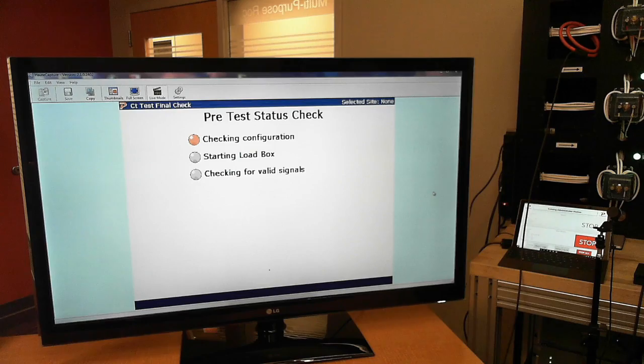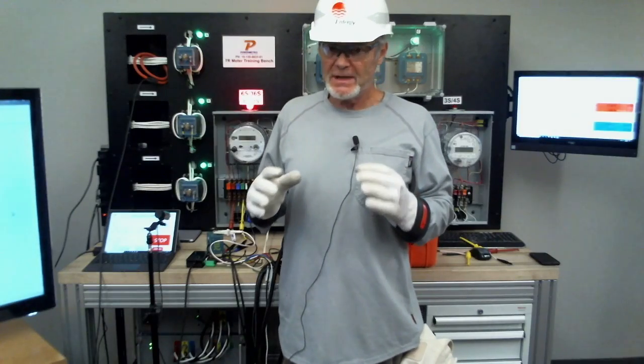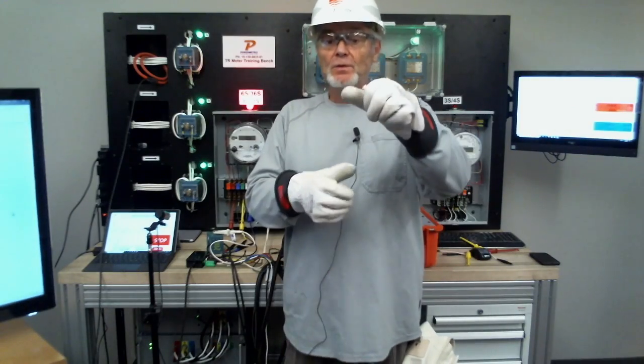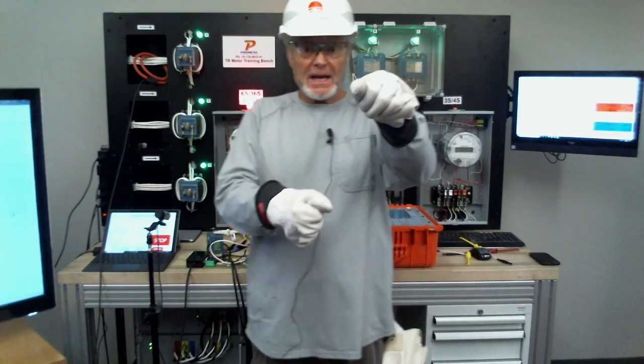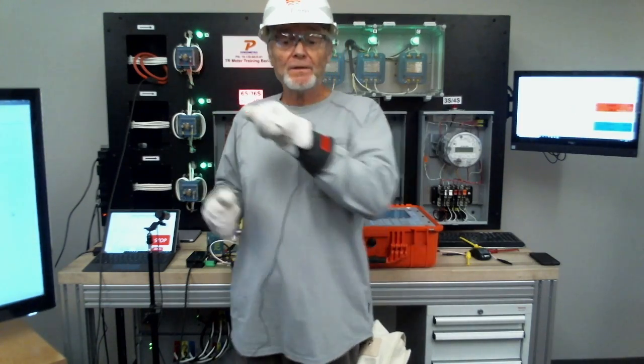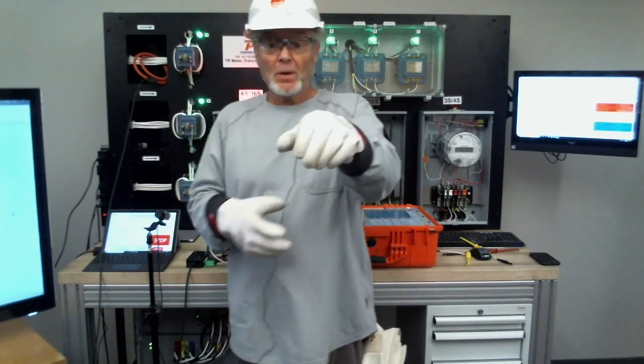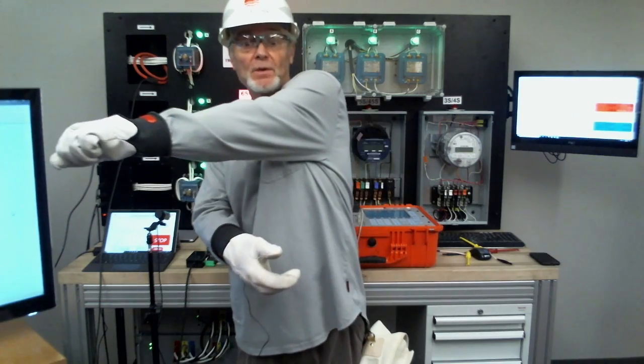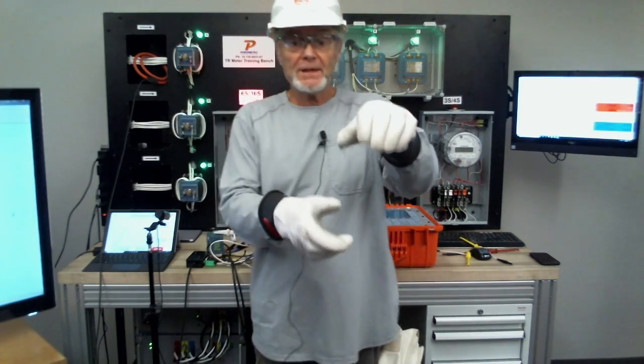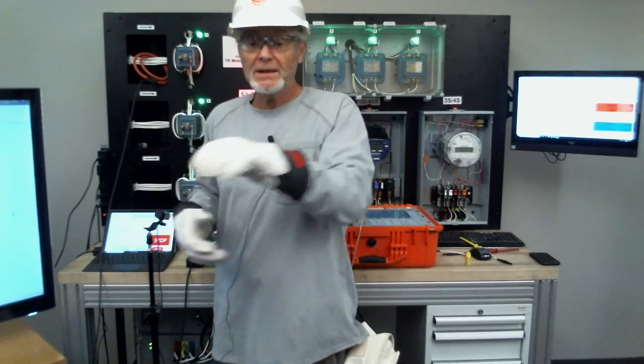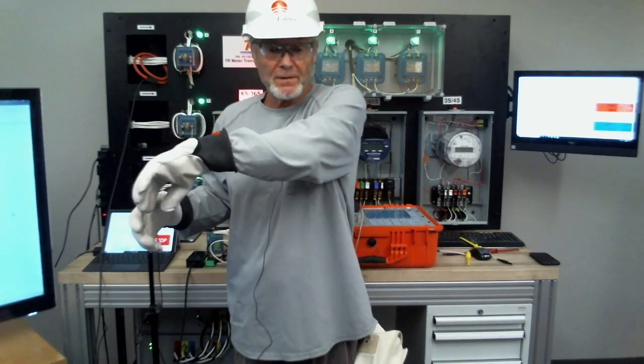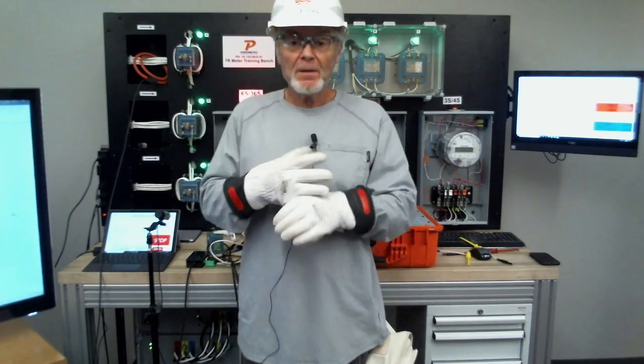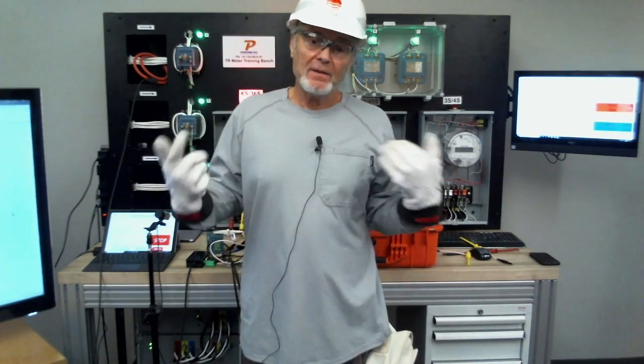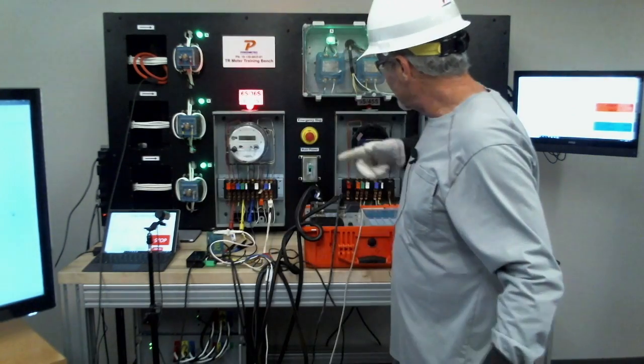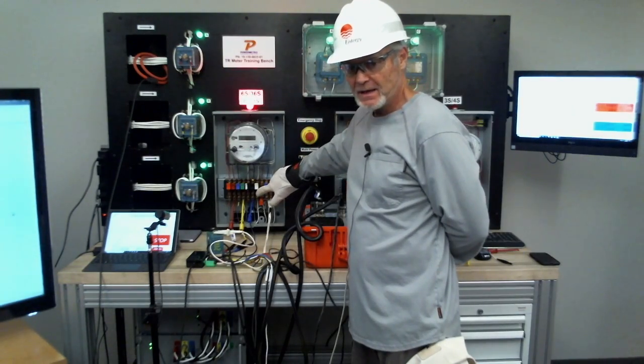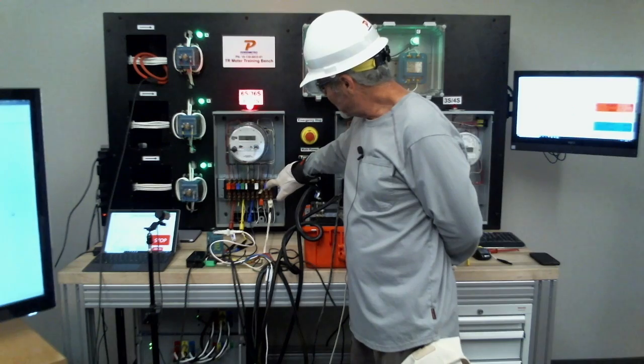So things to always be thinking about when you're doing a load box test, okay? Do not, when you finish phase A, disconnect both and move to phase B, okay? Don't leave one of your connections connected and move over to phase B, okay? So disconnect both of them and then move everything, disconnect everything and then move everything over to phase B, okay? Think about the in and the out and the white and the black, okay? Remember, you're going to need some sort of a separator up here, okay? You've got to separate them if you're going to use this.